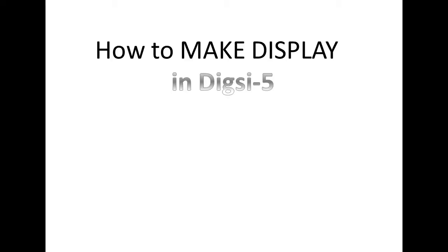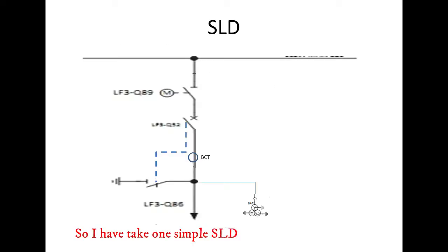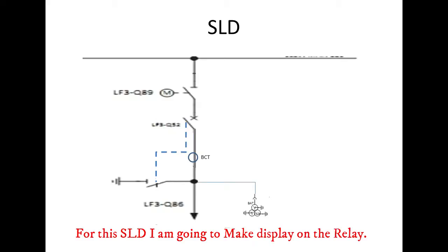In this video I am going to show how to draw a display in DIGSI 5. So I have taken one simple SLD. For this SLD I am going to make a display on the relay.